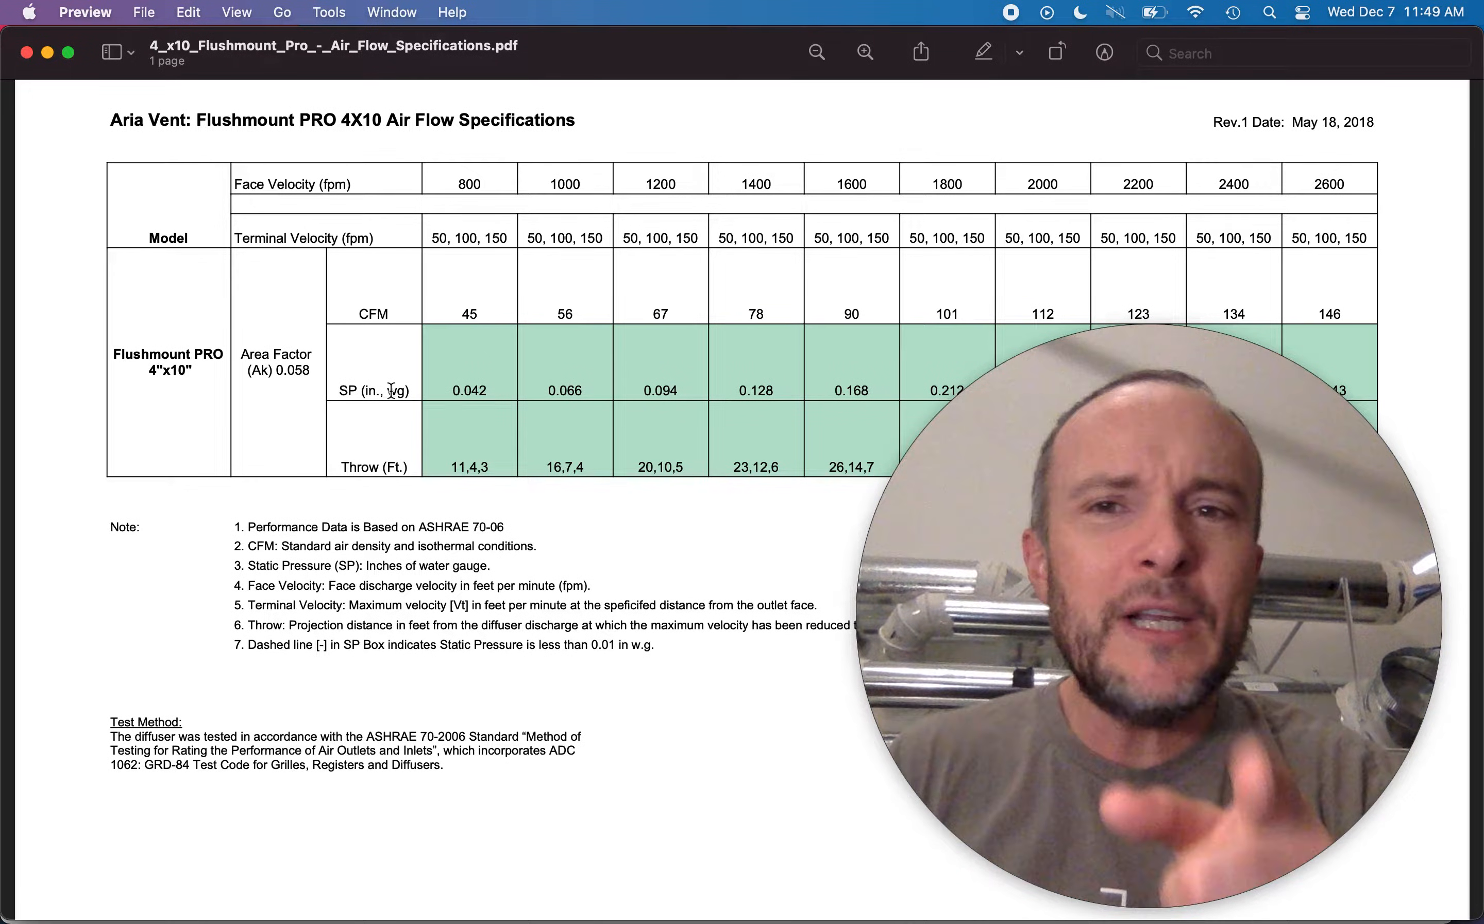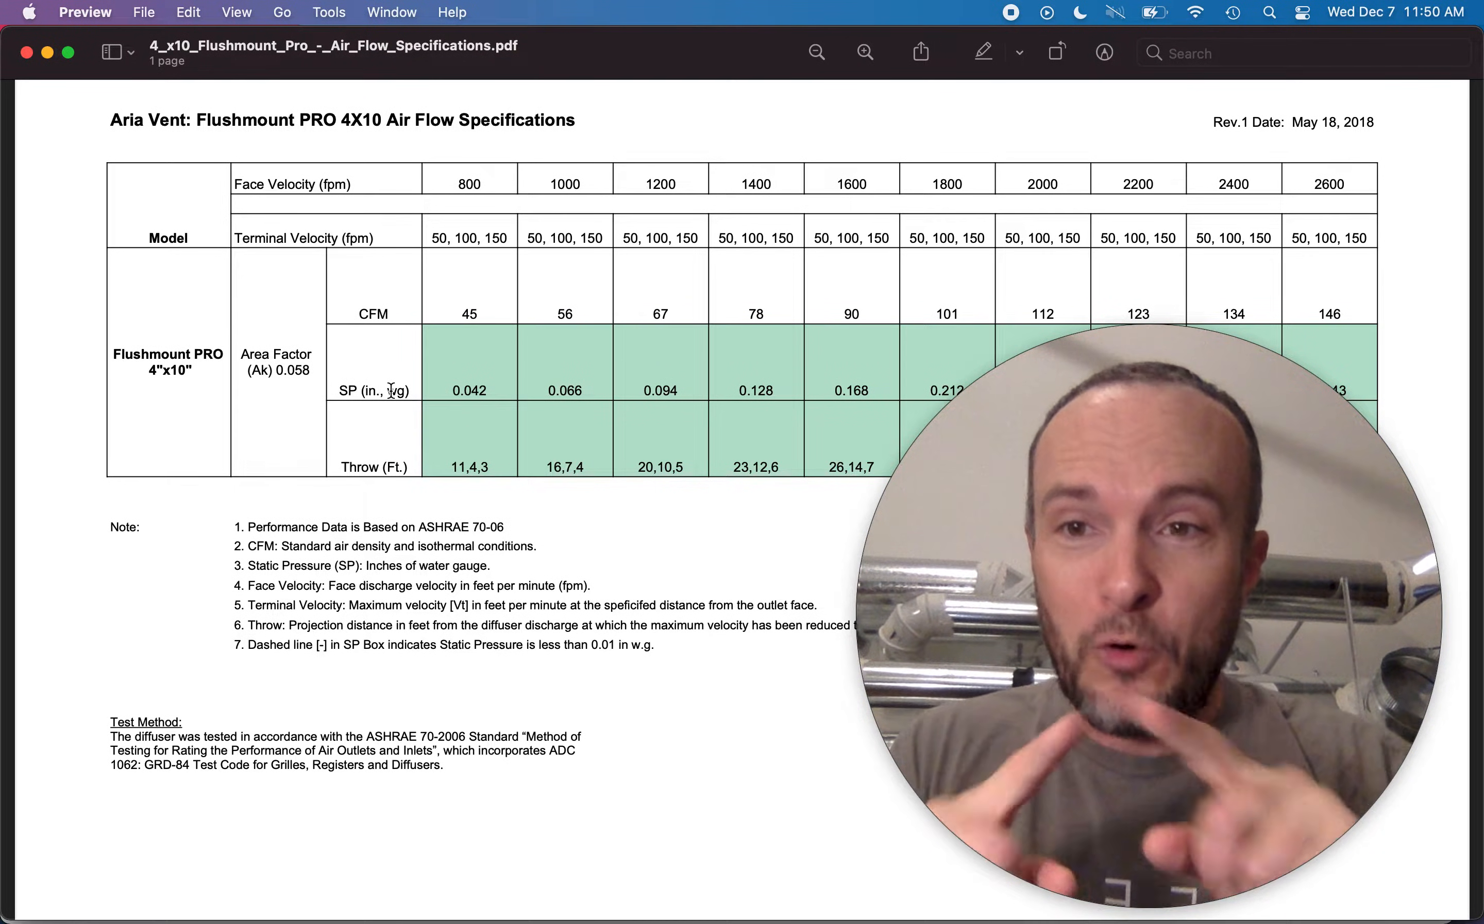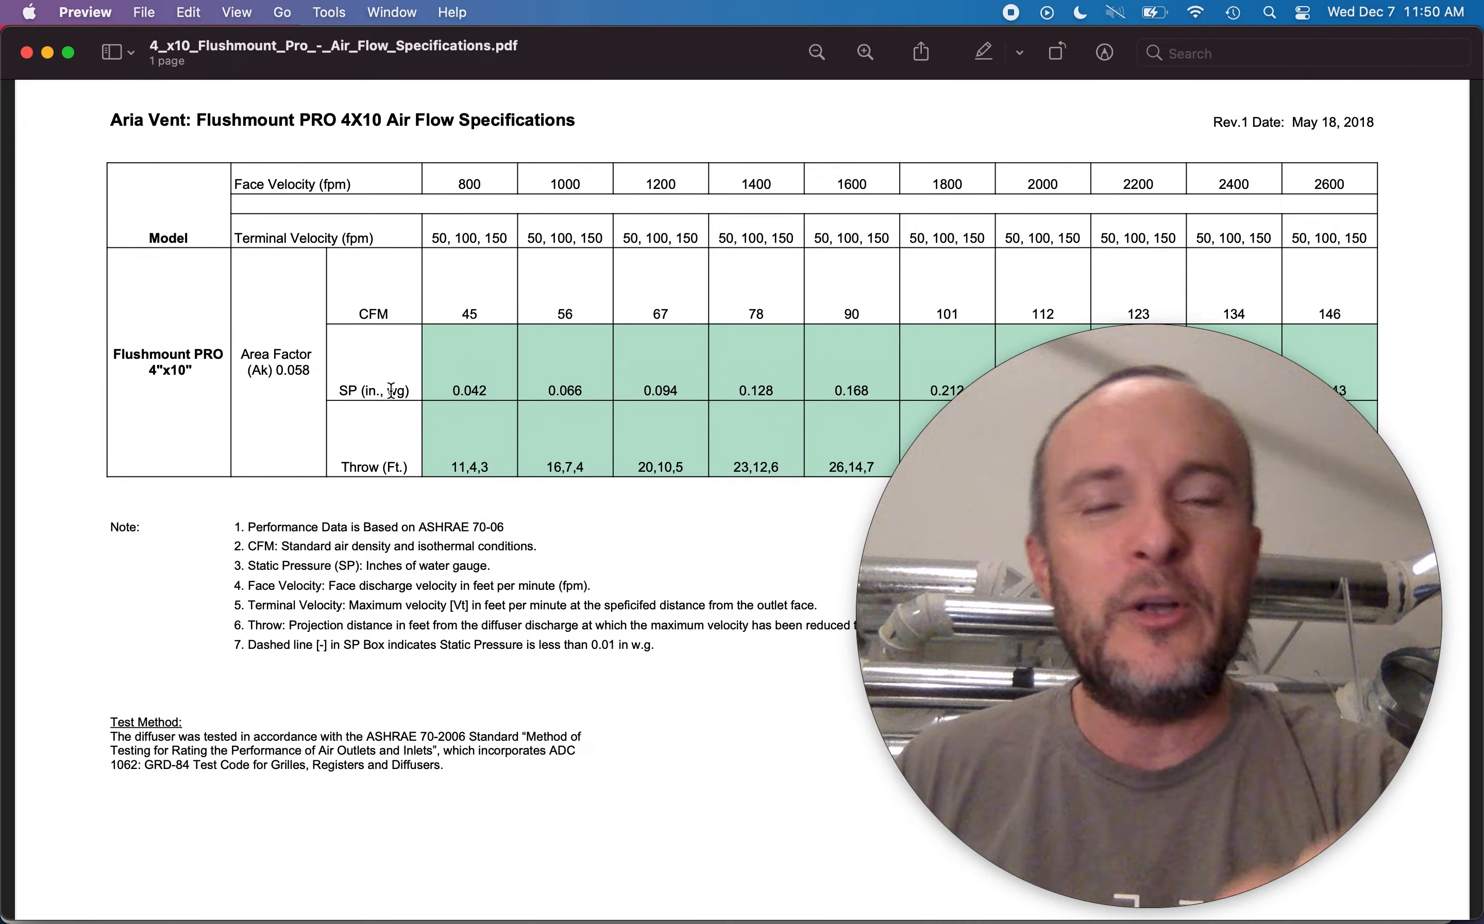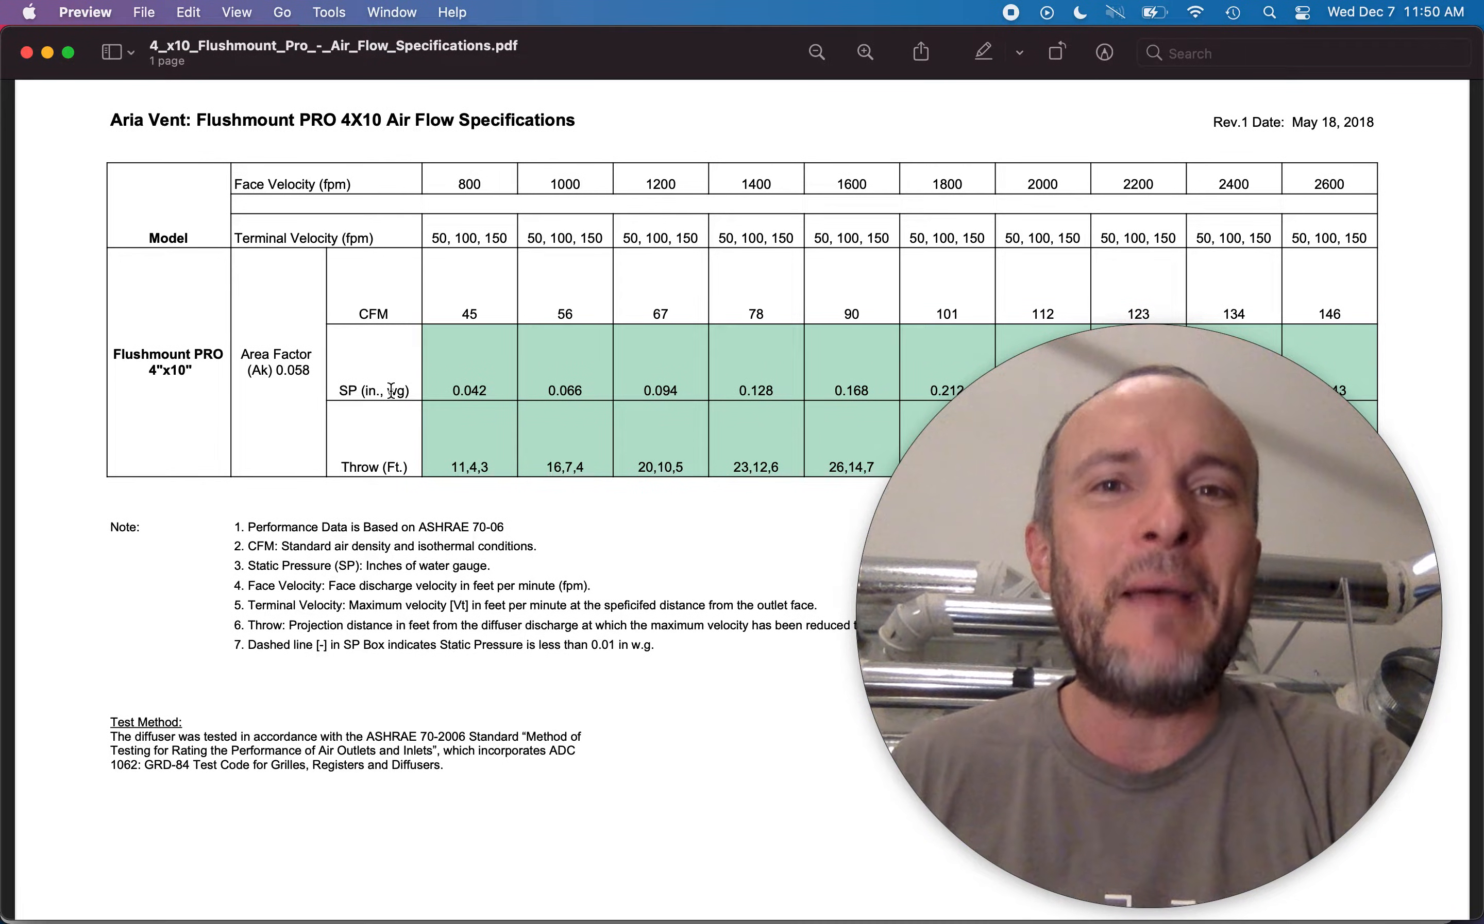So really what we're going to do is we're going to take this 800 number, cut it in half. So the CFM coming out of an 800 feet per minute 4 by 10 which only has a net free area of about 9 square inches is really going to be not 45 but 22 and a half. Just imagine that.